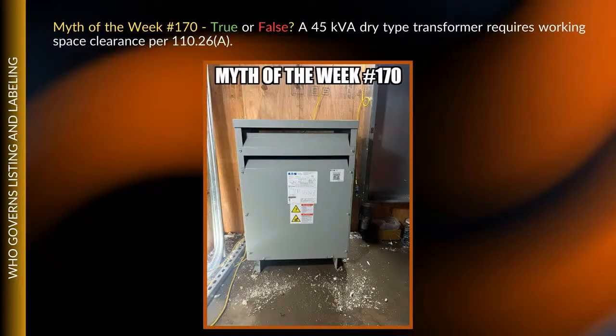I want everybody to pay real close attention to that, because I'm going to explain when you don't have these working clearances, the things you do in order to apply additional protective measures to verify it's de-energized. You'll suit up and everything, but you'll verify everything's de-energized. And once it is, then you can put your infrared thermography on there to test everything.